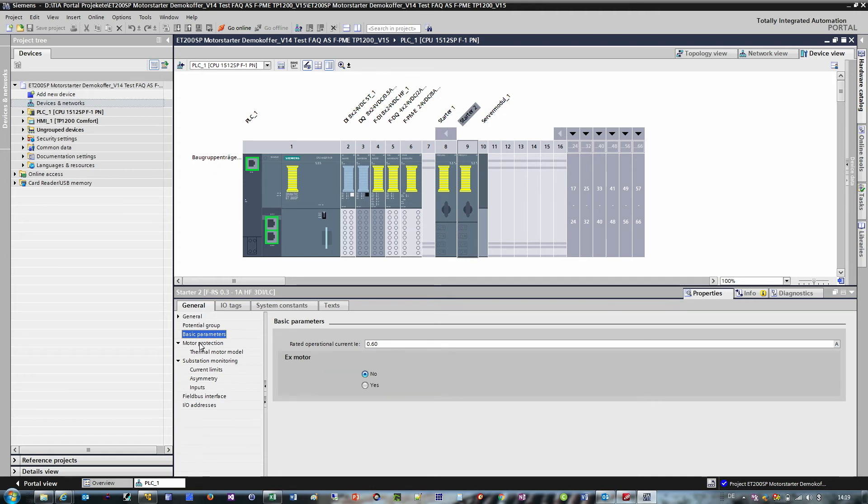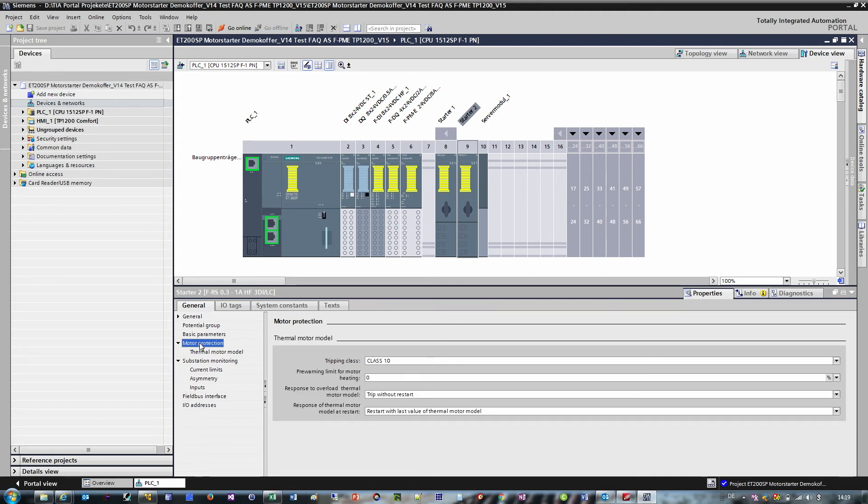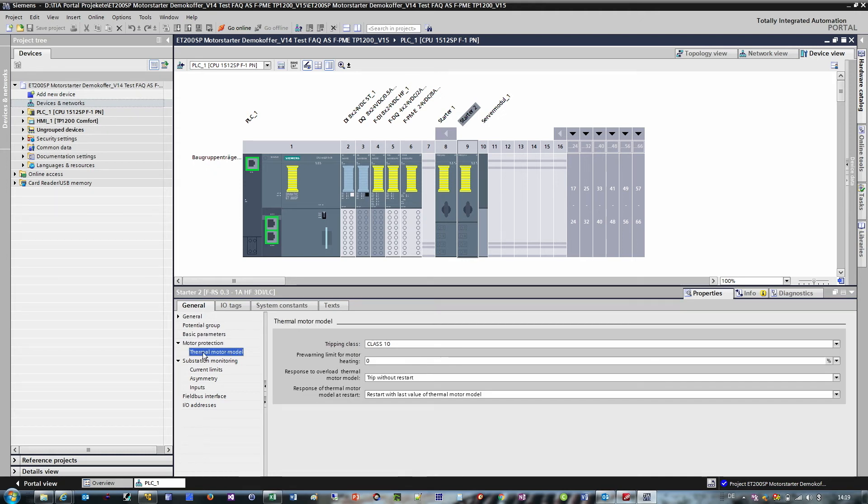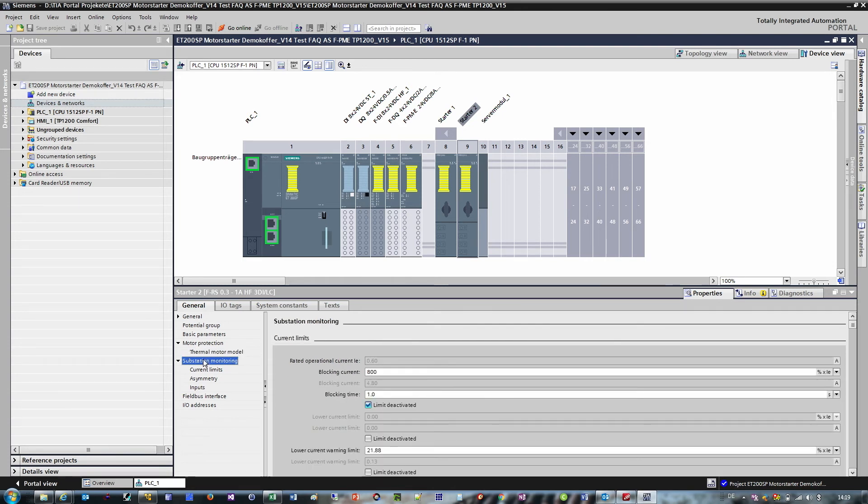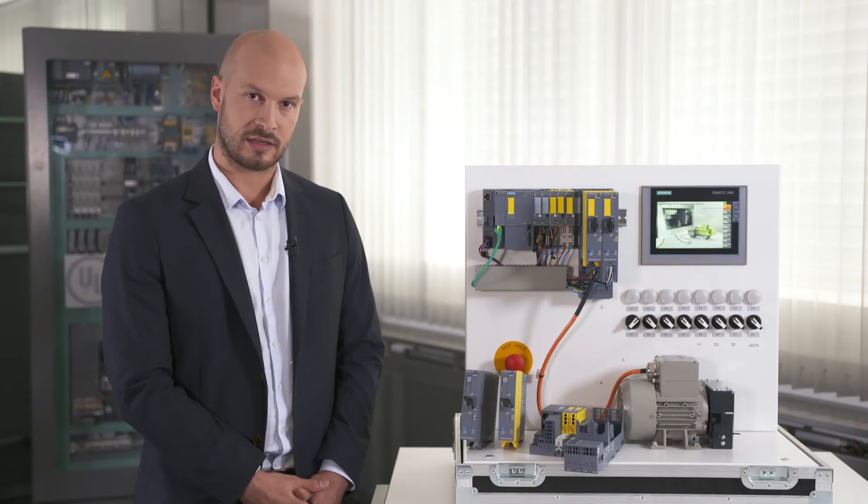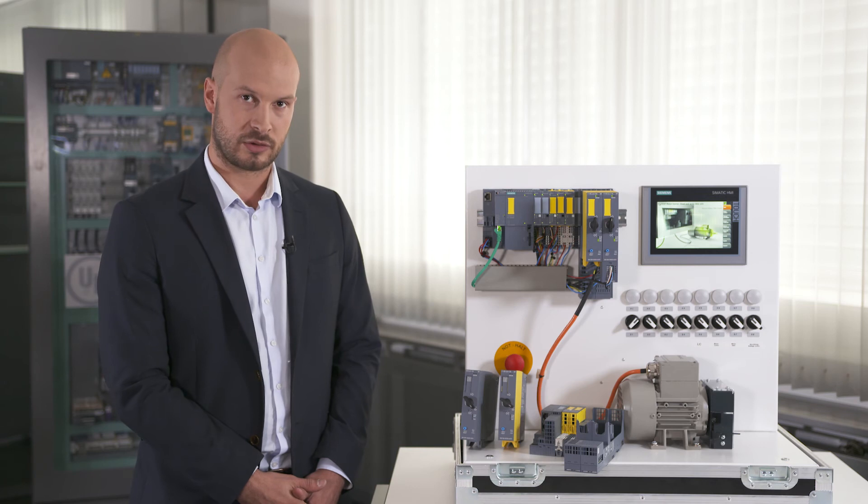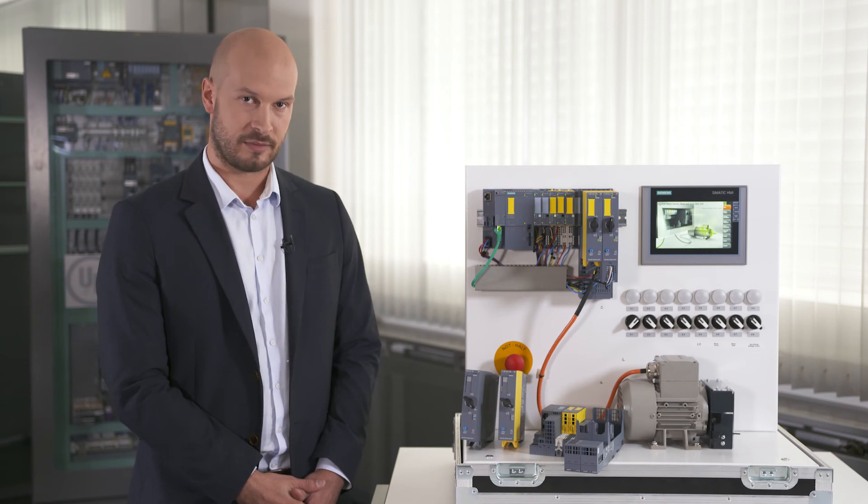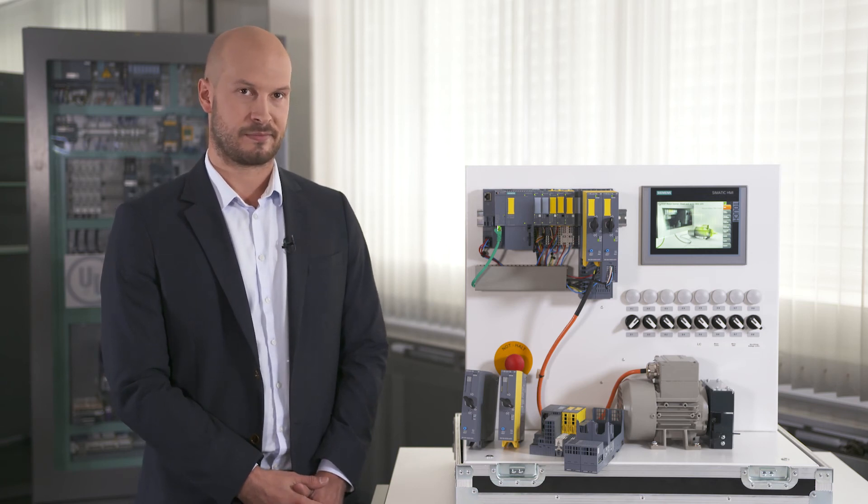Only the motor current is a must here, but you are able to change the motor protection class. You can choose between single phase and three phase load and you can also have the option of parameterizing appropriate warning thresholds and trip levels for your application.